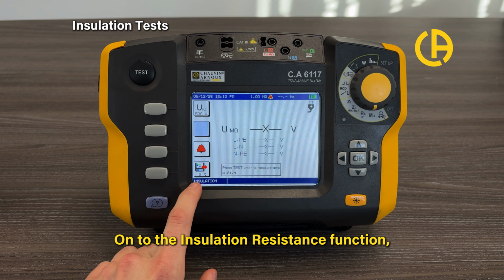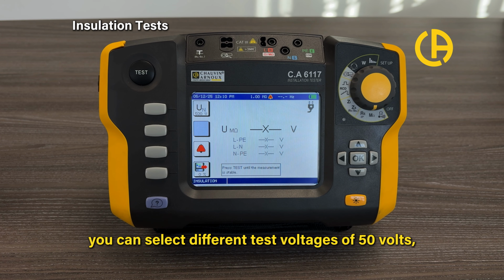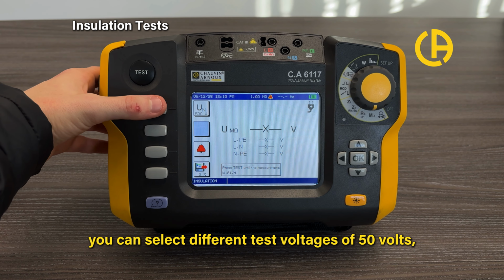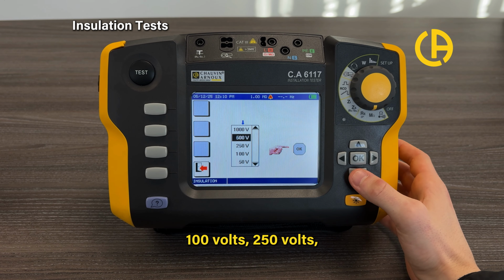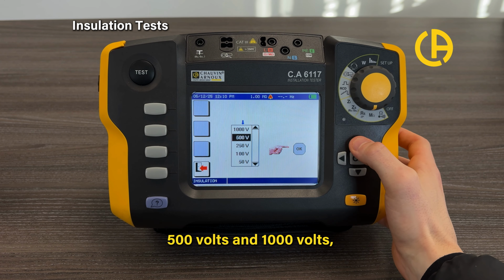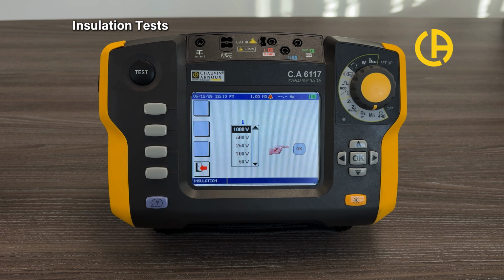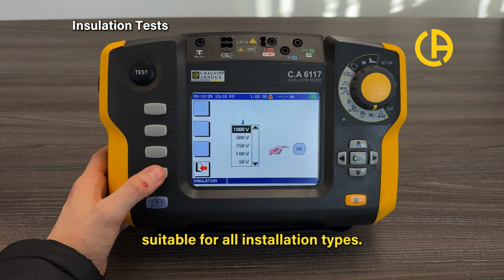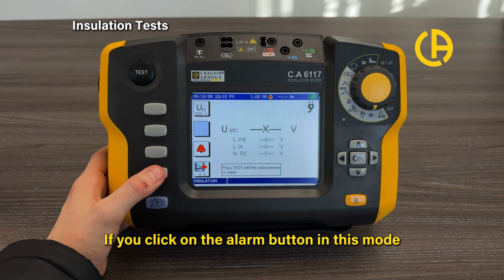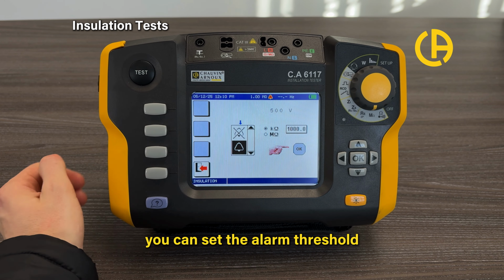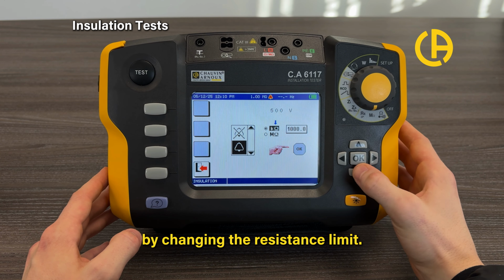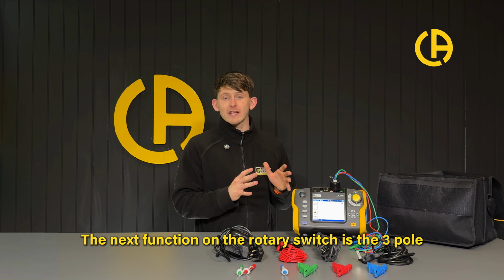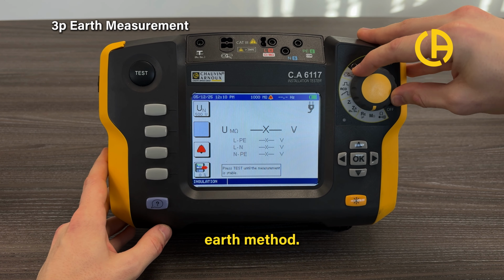Onto the insulation resistance function, you can select different test voltages of 50 volts, 100 volts, 250 volts, 500 volts and 1000 volts, suitable for all installation types. If you click on the alarm button in this mode, you can set the alarm threshold by changing the resistance limit. The next function on the rotary switch is the 3-pole earth method.